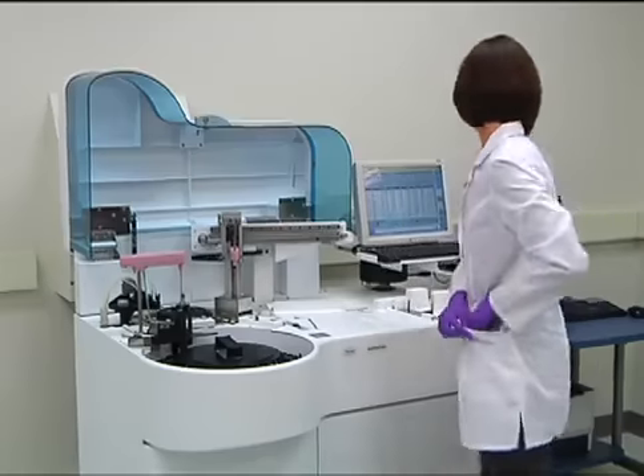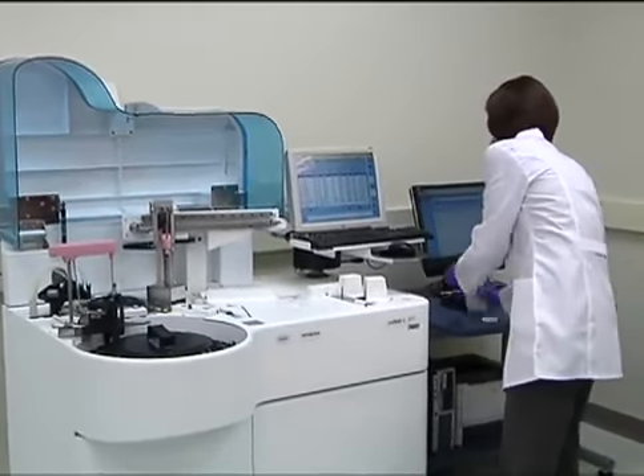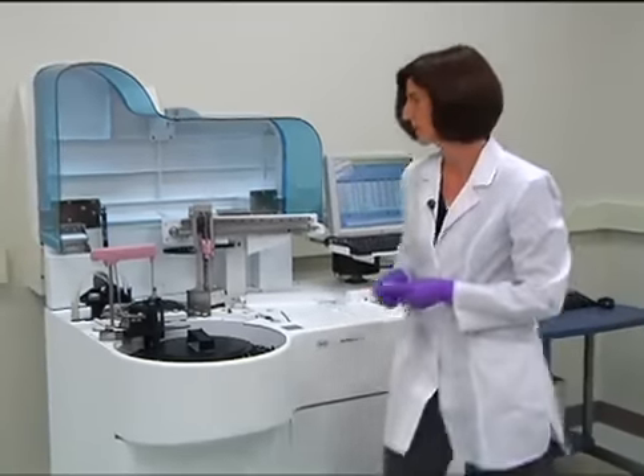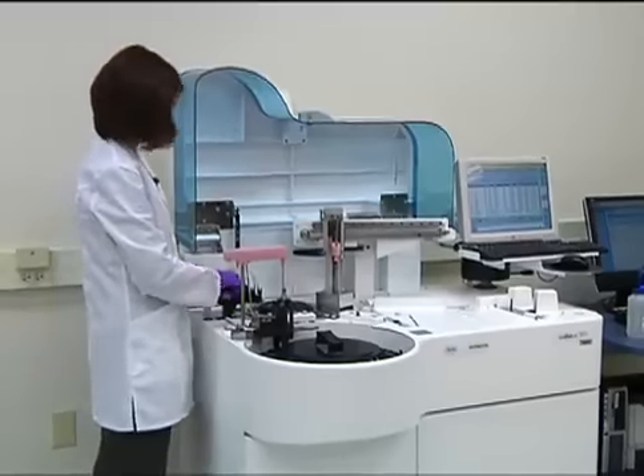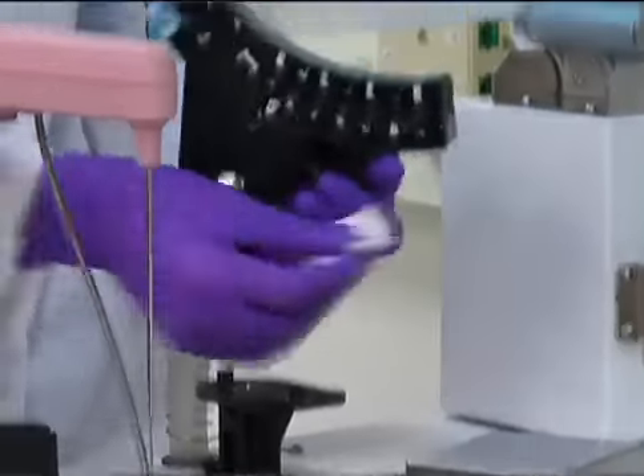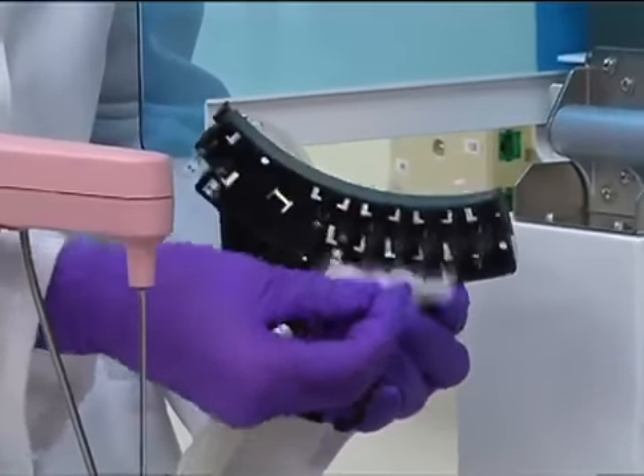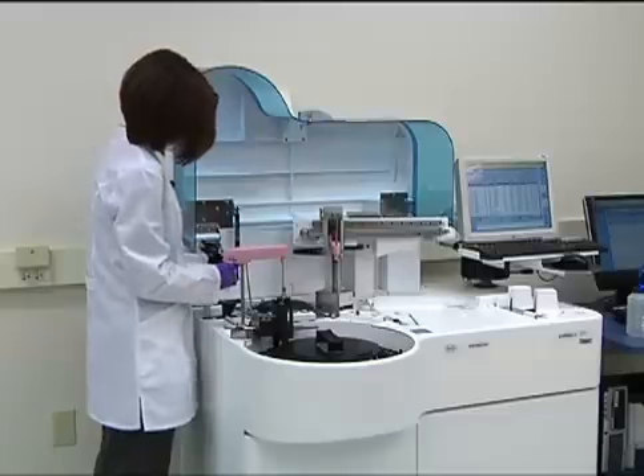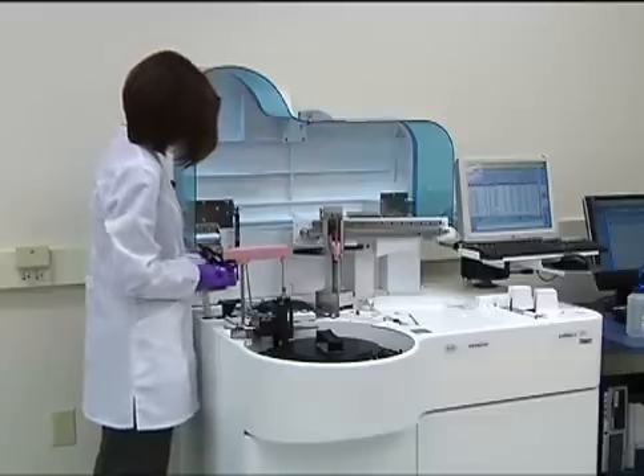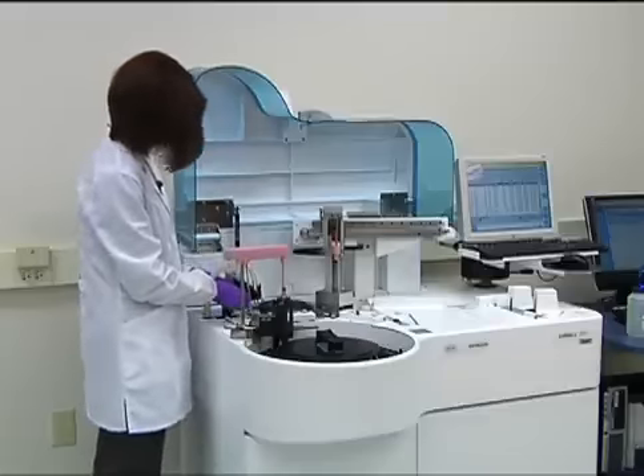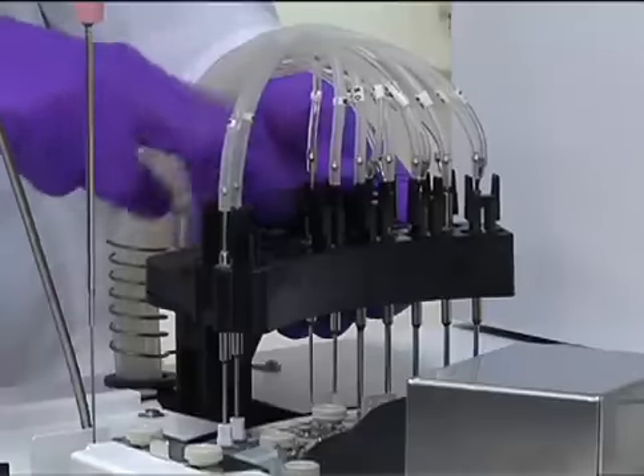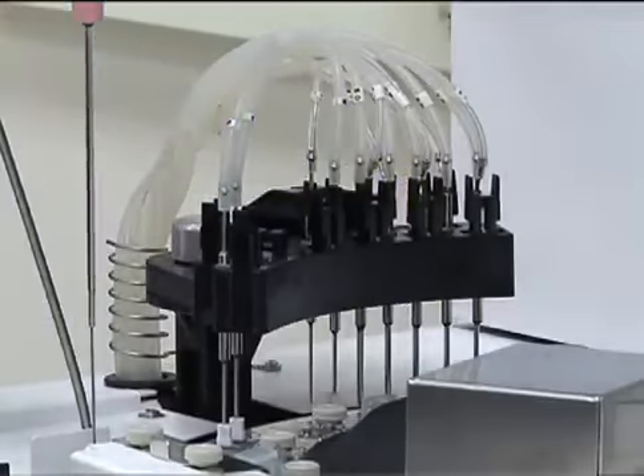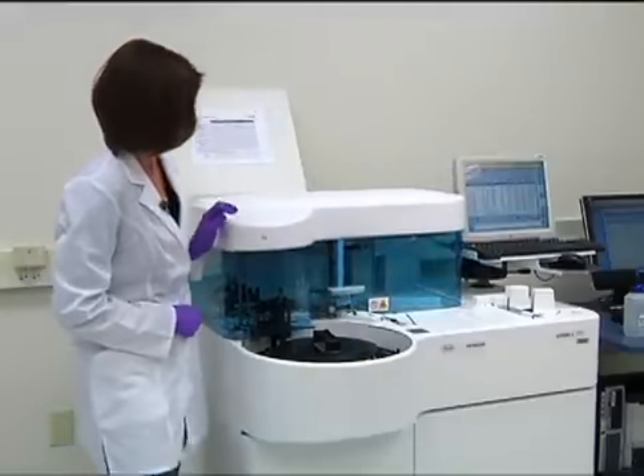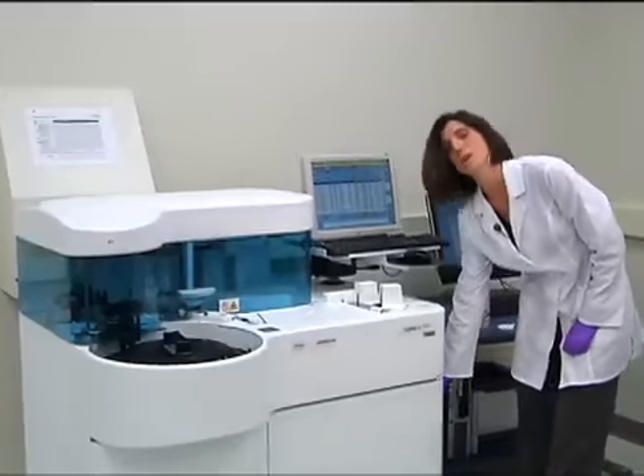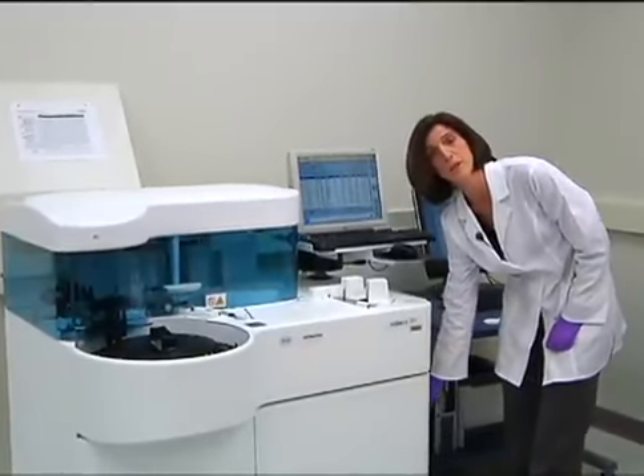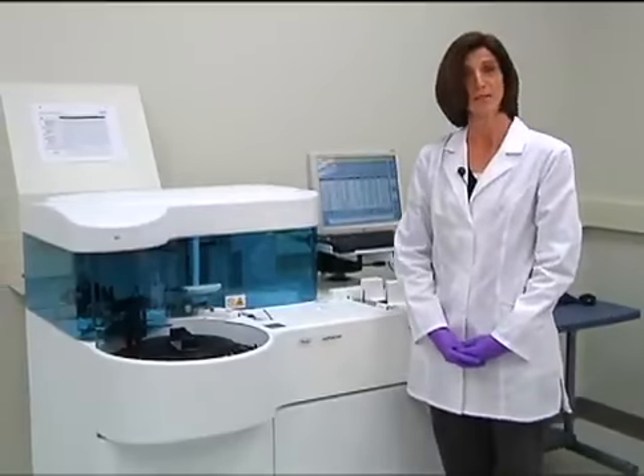Now we're ready to clean the cell rinse unit. And we need to have DI water on gauze. We will loosen the cell rinse unit and then just lift up on the unit and wipe the nozzles clean. Once all nozzles are clean, we'll return the cell rinse unit to its place. After completing the cleaning, we will close the cover. And then on the side of the instrument, flip our toggle switch back to the operation mode. And that completes our hands-on maintenance.